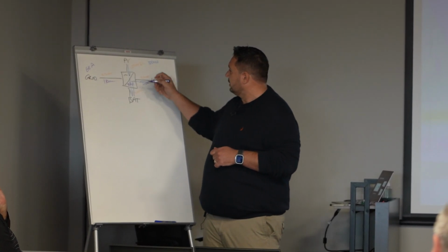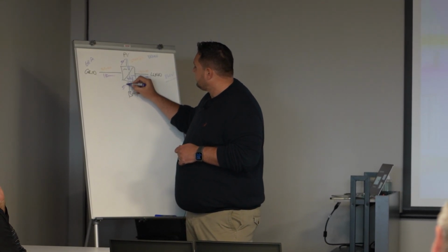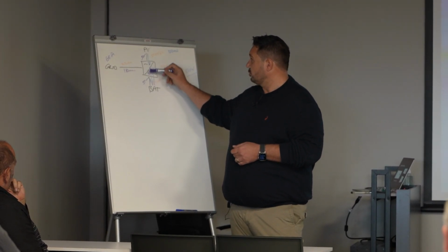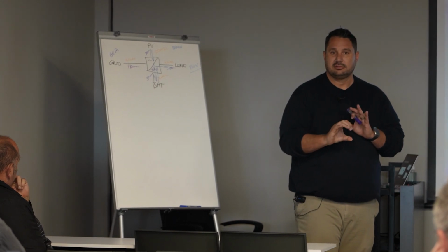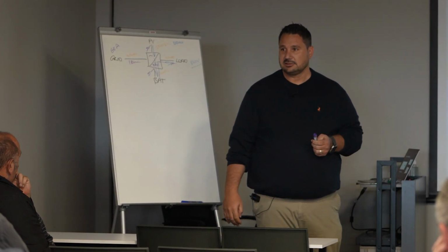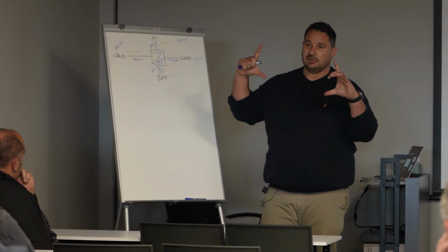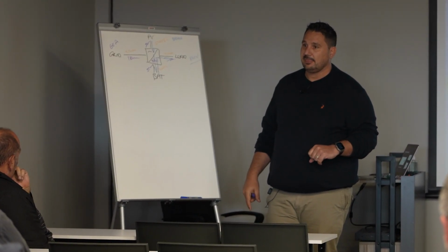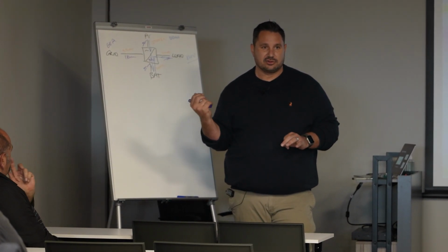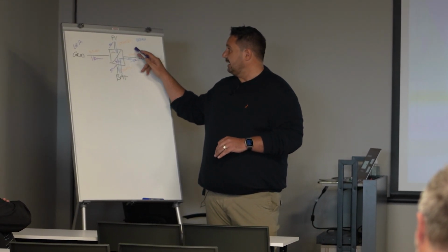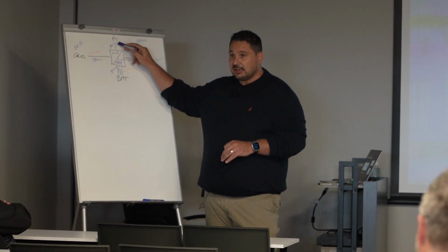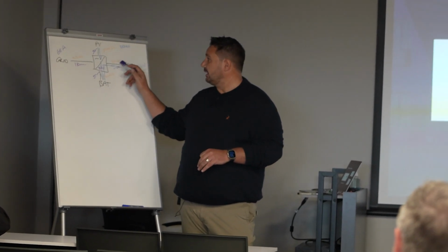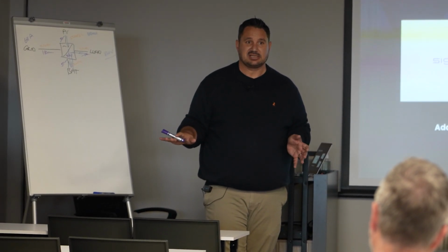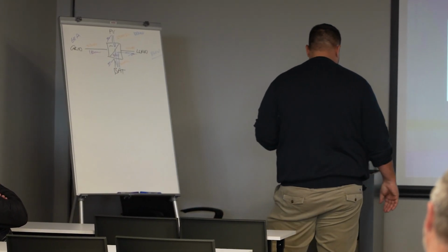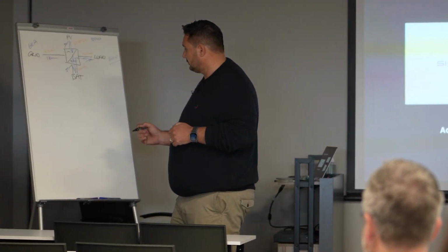That's it. So what you're basically doing is you're going, let's have a 50 millimeter pipe there and another 50 millimeter pipe there, and we join them all together, but we put a tap on. So we have got a source, a source, a source, and we're reducing it to only one way of getting it out. So even if this pipe was like 200 mils, and this was like a 300 mil pipe, putting that tap with that reducer in, that's the only flow that you're going to get out of it. And that is the total limiting factor. So if the load is 4 kilowatts here, that can only deliver 4 kilowatts to the battery. If the load is 8 here, you are not charging batteries. There's no way it's happening. So on a grid-tied system, what does it look like?